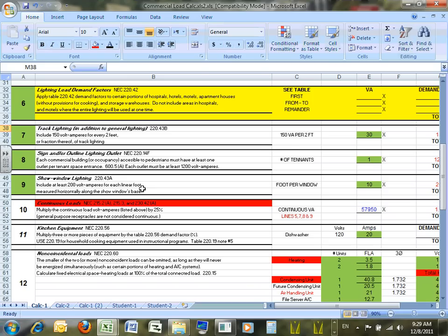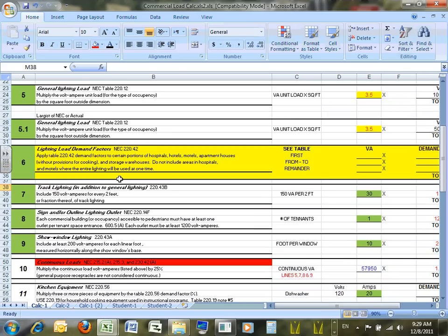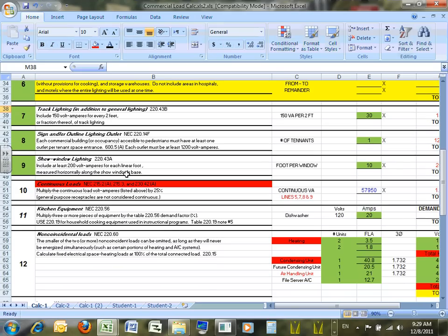You're going to take them by volt amps. You're going to add a step for parking lot light and security lights as a volt amp. Find the volt amp when you guys design them. You find the volt amp for all of them, add them up, and that will be the load for the security light, for the perimeter lights, as well as the parking lights. Okay. Any question guys up to this point?